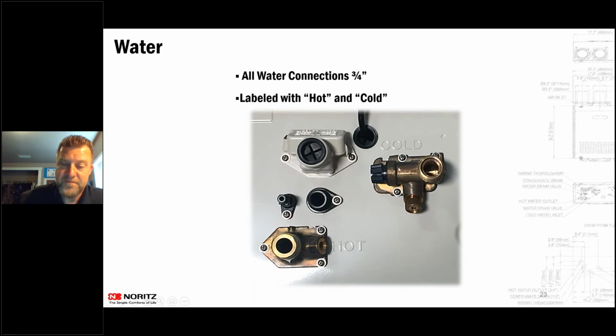But the hot and the cold are always going to be labeled there. So hot and cold and gas. The gas is usually a different color than the water connections. The water connections are usually a copper brass color, and the gas connection is a silver color. Nothing will void your warranty on a tankless water heater faster than hooking the cold line into the gas connector on the bottom of the unit. And I say that not to be funny, because we've seen it multiple times where people have hooked that up wrong. So just make sure that you are hooking up the correct things on the bottom.